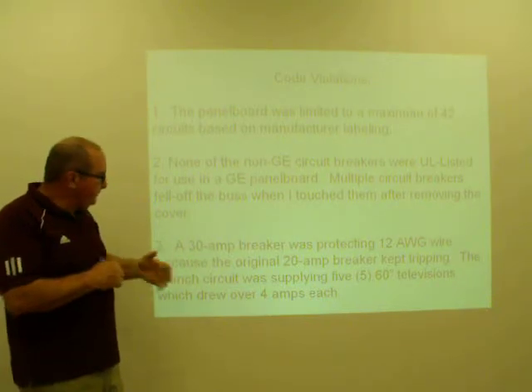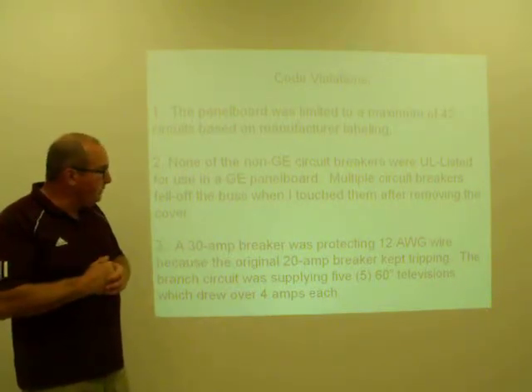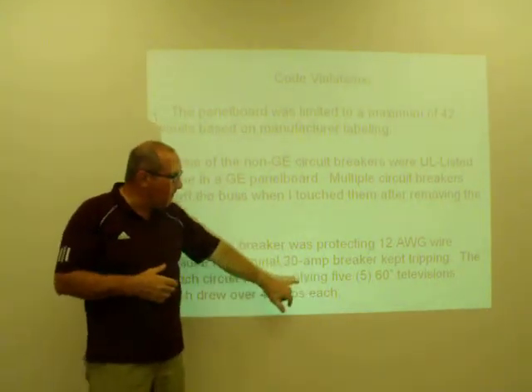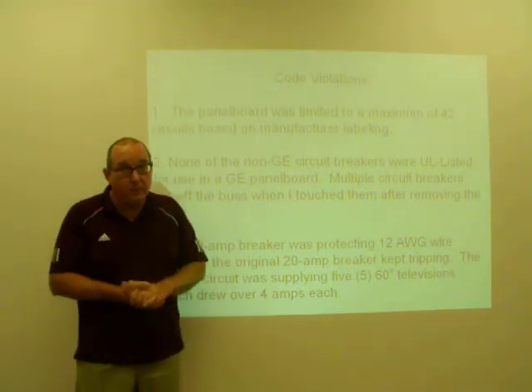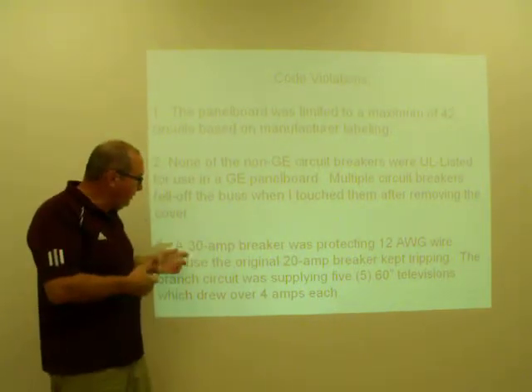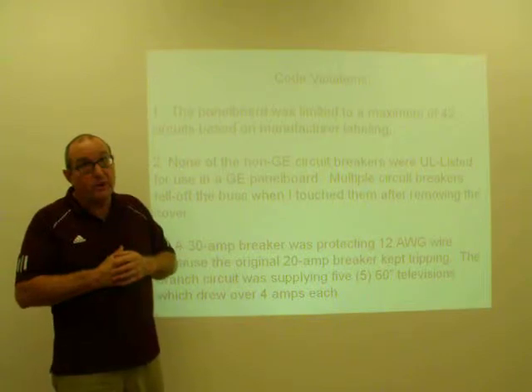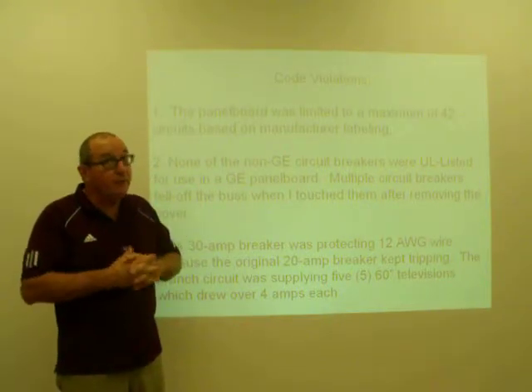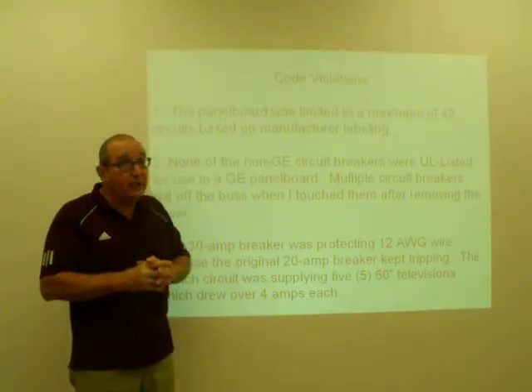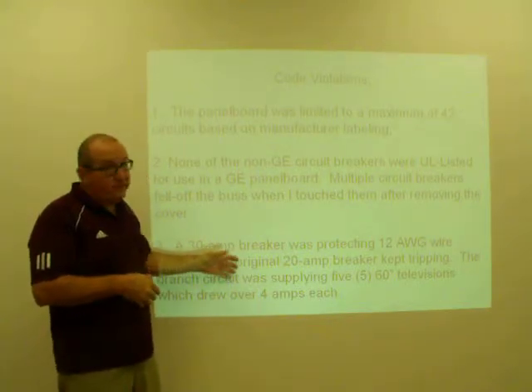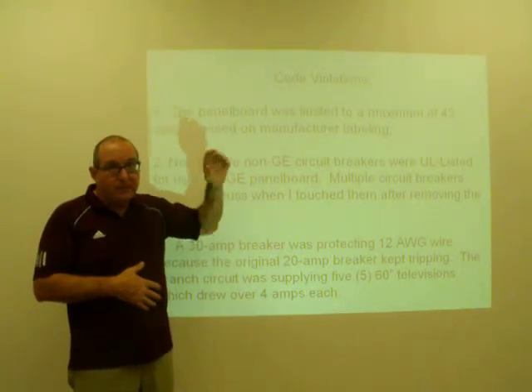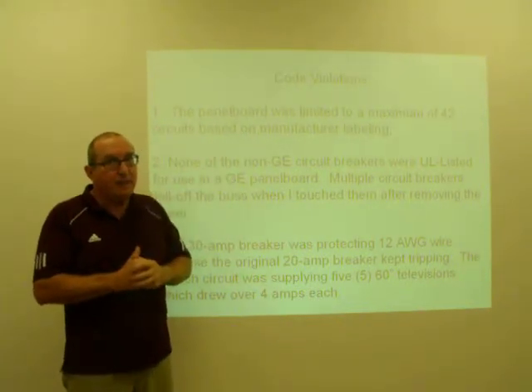There was one other major code violation where there were 5 large TVs on a 20 amp breaker. The breaker kept tripping, so some bright individual went in and replaced that with a 30 amp breaker. Stopped the breaker from tripping. TVs stayed operating. It was very easy to trace the circuit as I just went through the false ceiling, feeling for which piece of MC cable was hot.